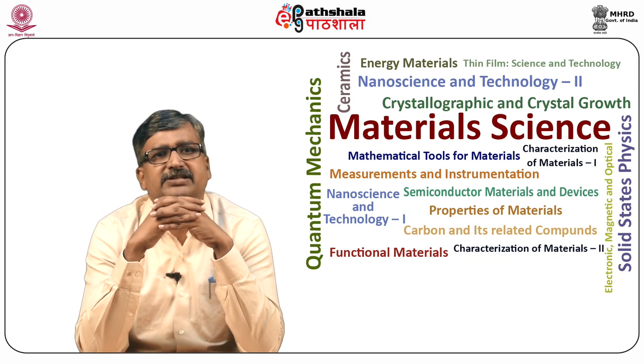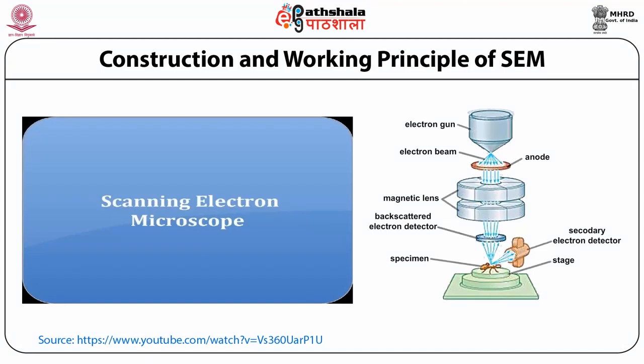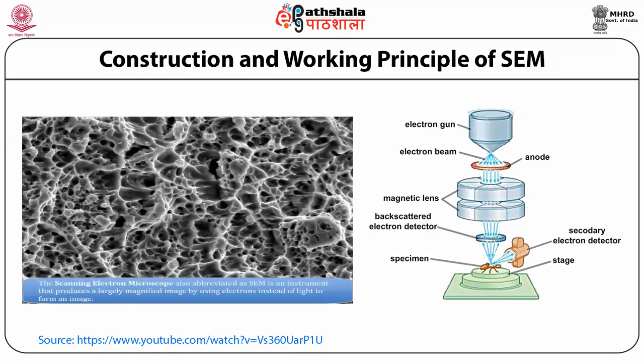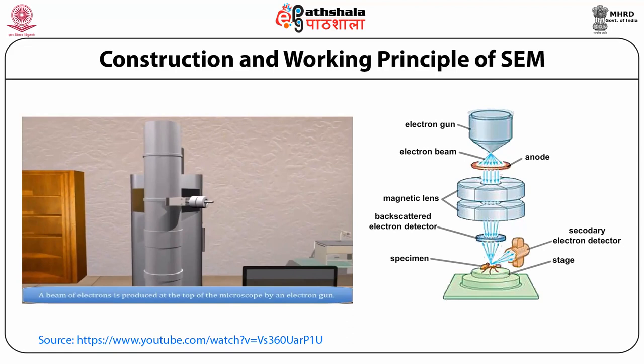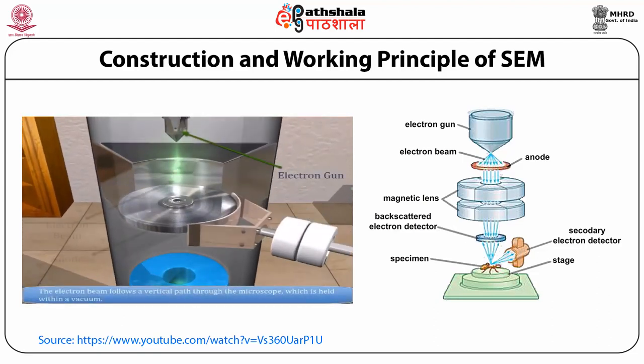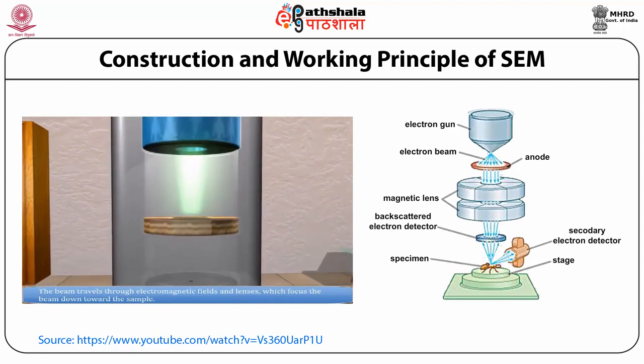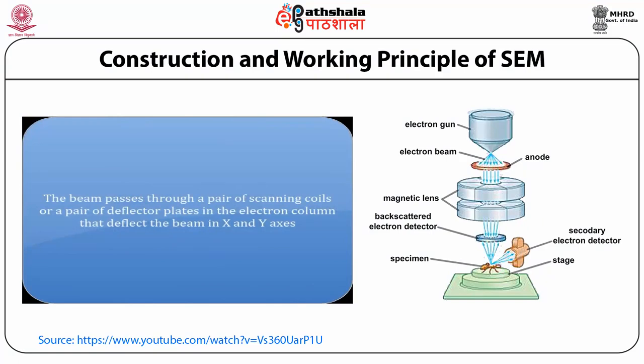The scanning electron microscope is an instrument that produces a magnified image using electrons instead of light. A beam of electrons is produced at the top of the microscope by an electron gun. The electron beam follows a vertical path through the microscope, traveling through electromagnetic fields and lenses which focus the beam down towards the sample. The beam then passes through a pair of scanning coils or deflecting plates in the electron column, which deflect the beam in the X and Y axes.